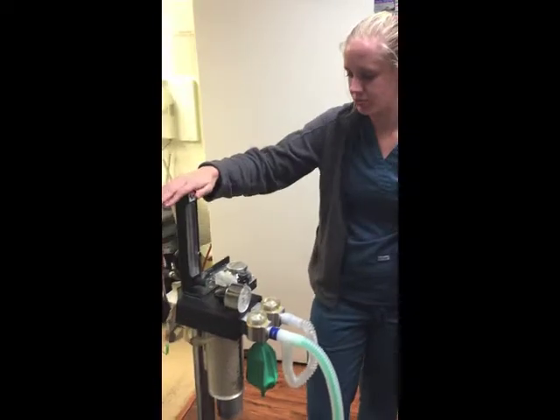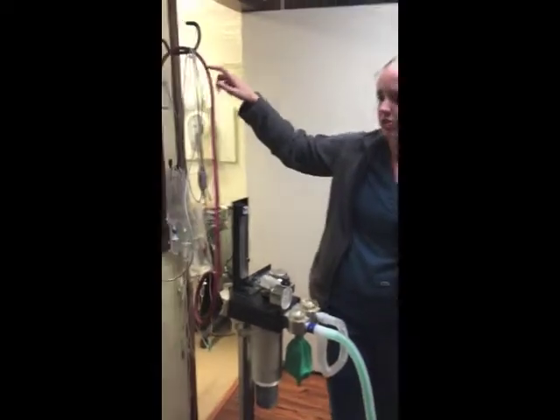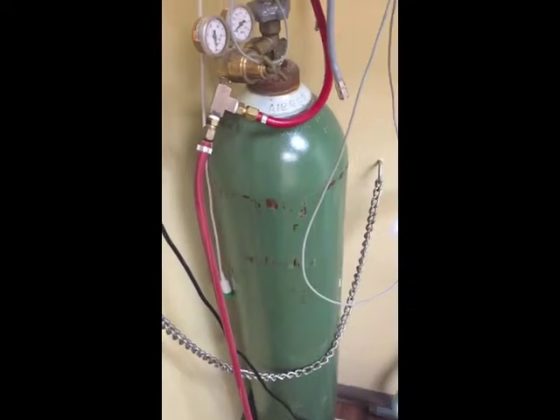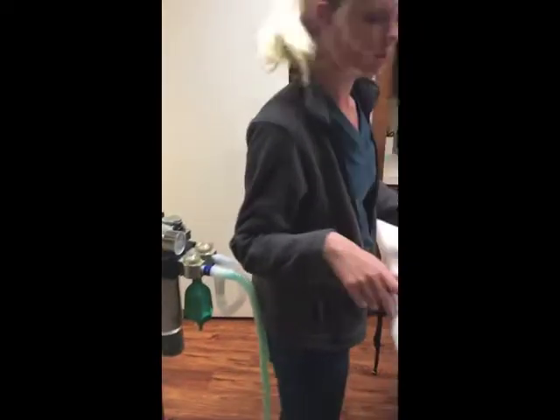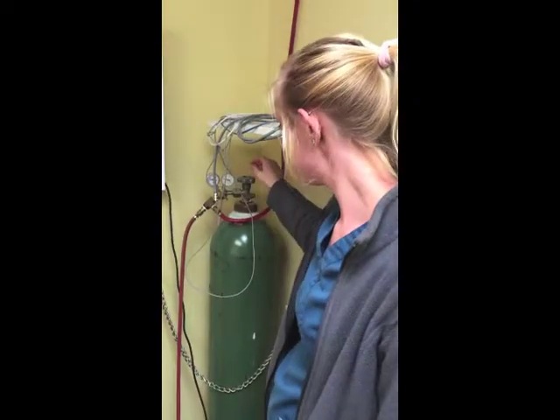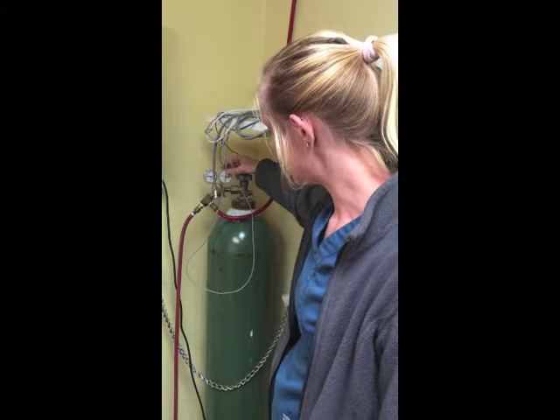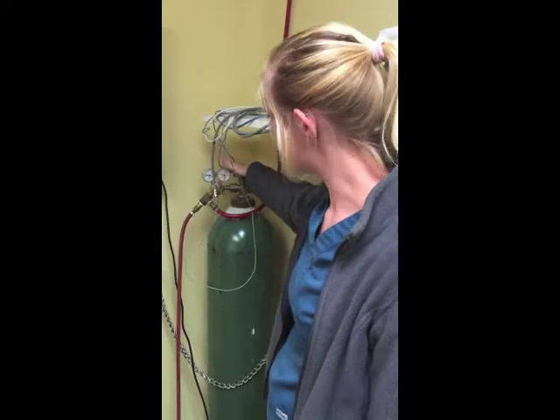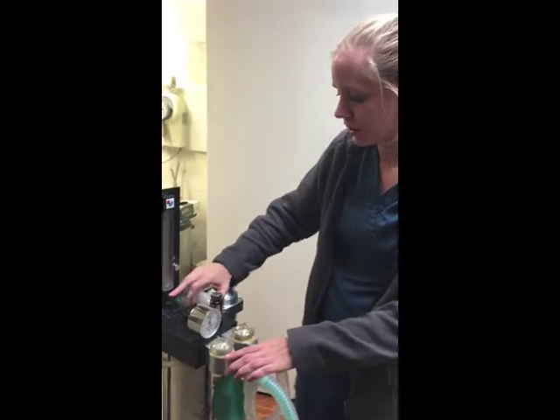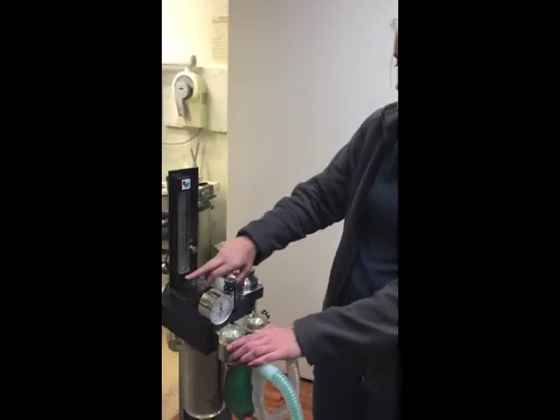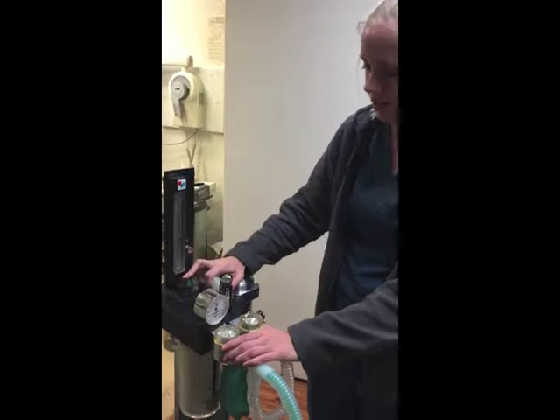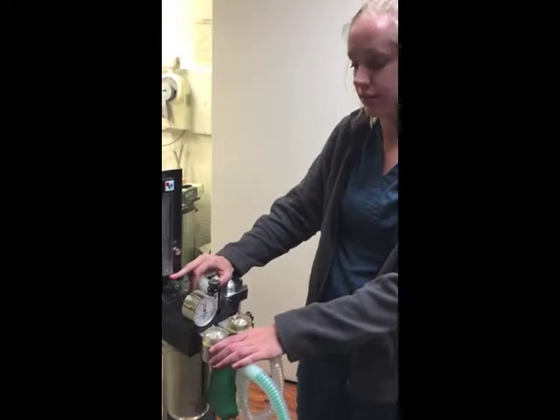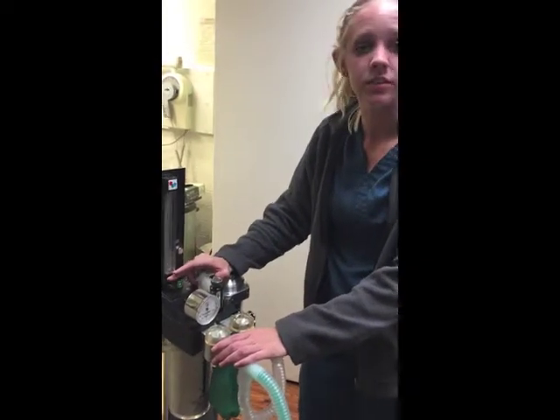This is our anesthesia machine, and as you can see, the oxygen tank is hooked up through here, and since we don't have a big enough room for a closet, it's chained up in the corner of the room. This is the pressure reducer valve. It regulates the oxygen leaving the tank so it's not too much PSI, and we have it set on this. This is the flow meter, and it allows us to decide how much oxygen the patient gets depending on the breed and the size of the patient.